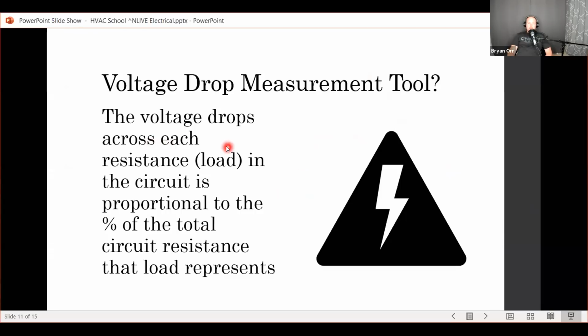All right, so voltage drop measurement tool. I'm going to read this line because it's a confusing line, but once you get your head around it, I think you'll find it really helps you be a better diagnostician. Think of your voltmeter as a voltage drop measurement tool. Okay, we've talked about that before, but here's the line. The voltage drop across each resistance or load, whether designed or undesigned, in the circuit is proportional to the percentage of the total circuit resistance that load represents.